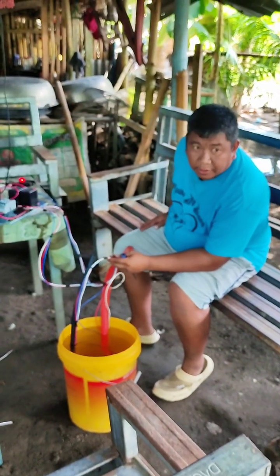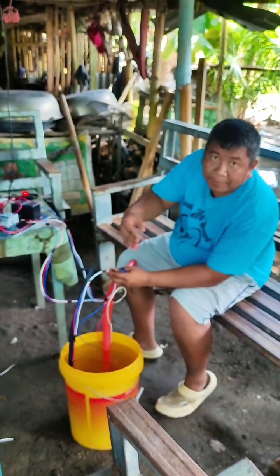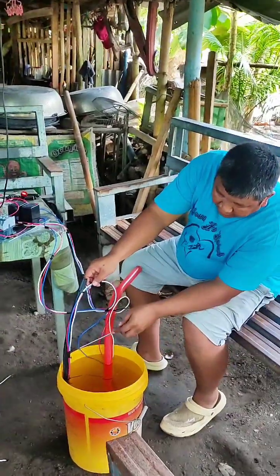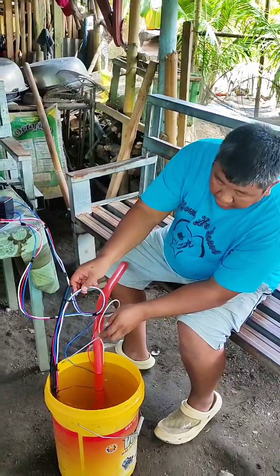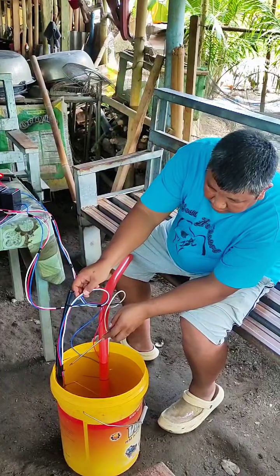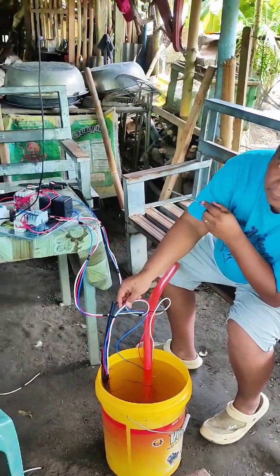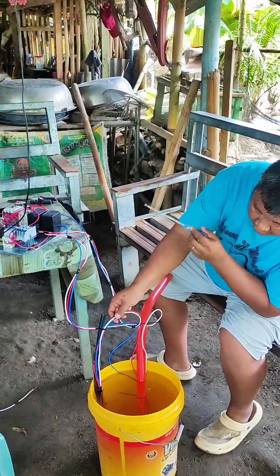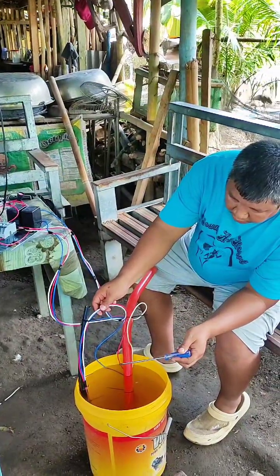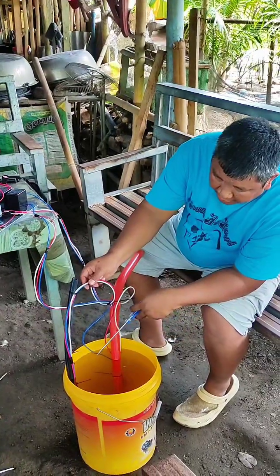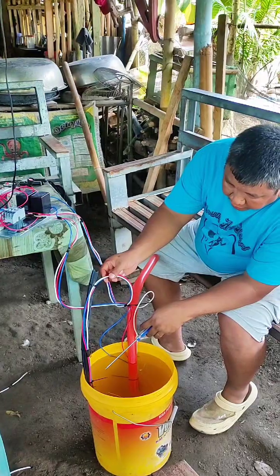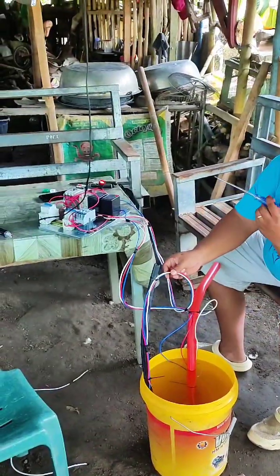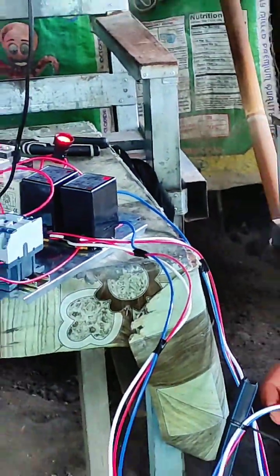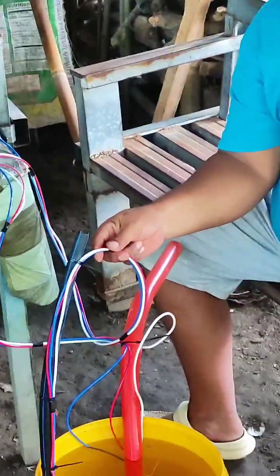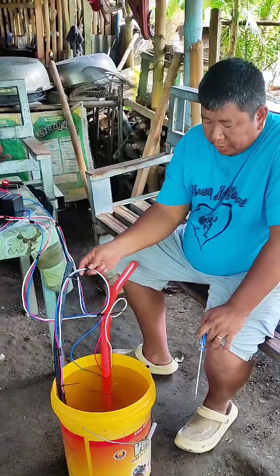For example, you were pumping continuously, and this simulates the tank. This is the upper sensor probe. When the water is full, it shuts off the pump, right? And then if the water is consumed, the water goes lower and lower until it reaches this lower probe here. If it reaches the lower probe, bam, the pump is on. The pump will turn on when the water in the tank is already lesser than half. And what about the well?